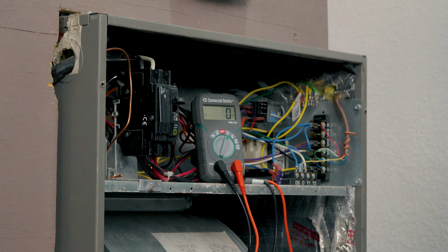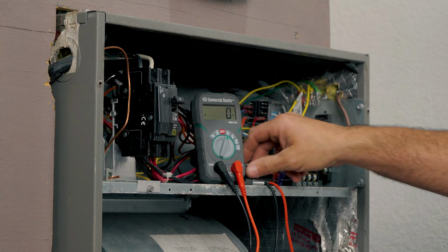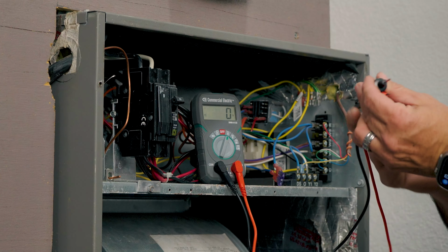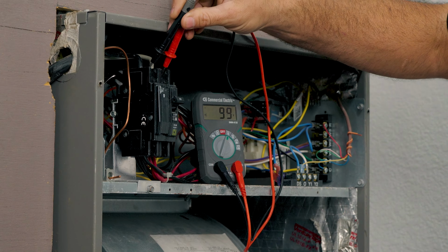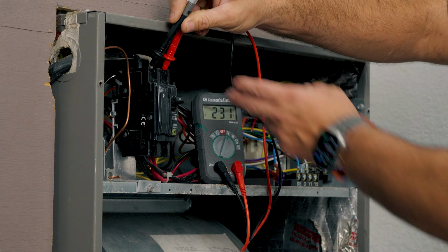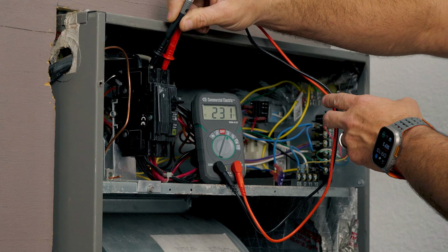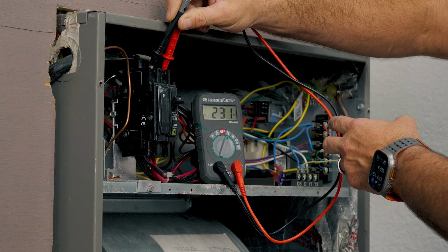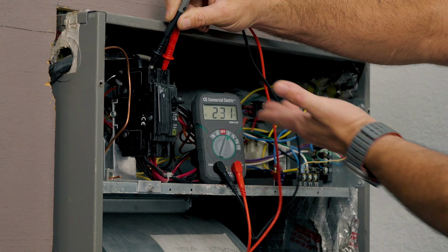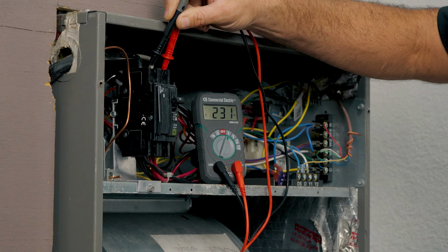The first thing we're going to test is if your system is getting high voltage. We're going to test across these 2 prongs right here, and verify that your system is getting between 120 to 240, depending on your configuration. This system is a 240, and we see 231. This is in the correct range.